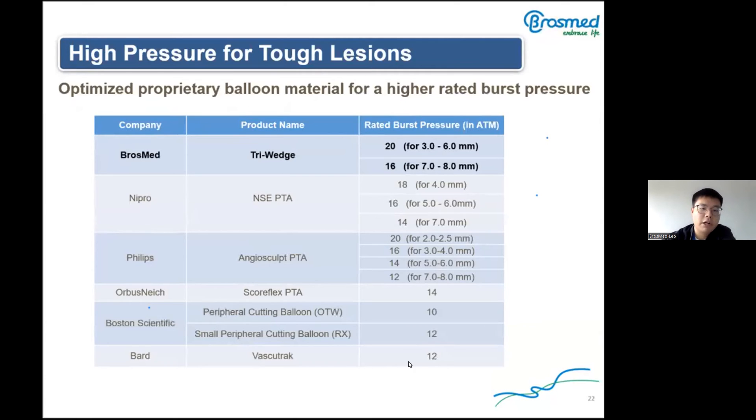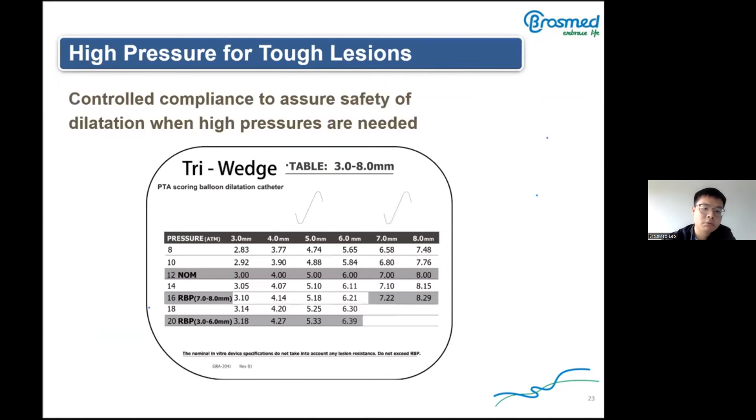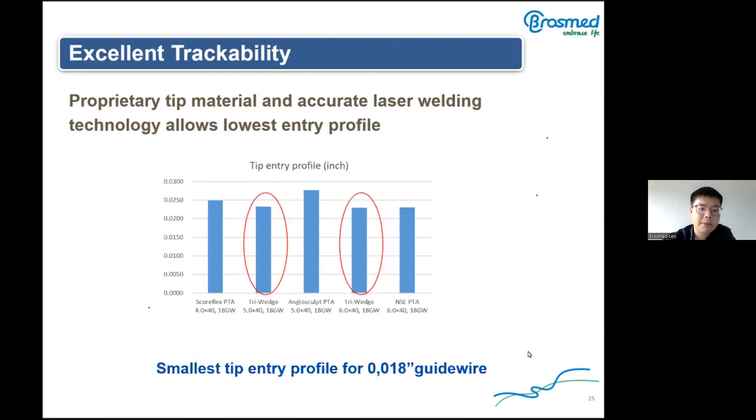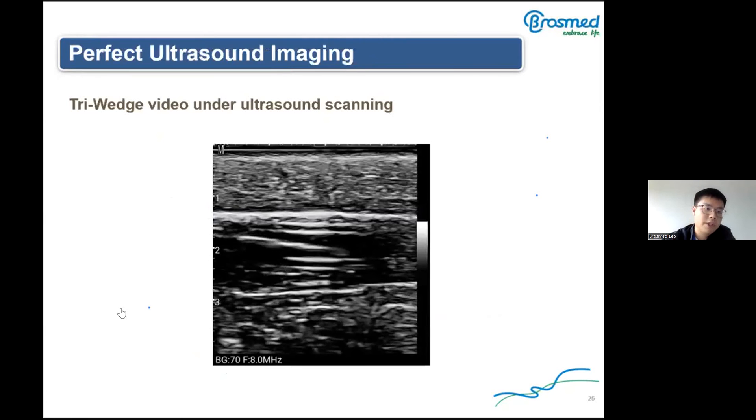Sometimes hard lesions require high pressure. The rated burst pressure of the Tri-Wedge is higher than similar competing products, indicating it can be safer during surgery. The Tri-Wedge uses a non-compliant balloon, so under different pressures the diameter changes very little, achieving accurate vessel dilatation. Accurate laser welding technology allows the lowest entry profile, improving the product's trackability and crossability. Compared to products on the same configuration, the tip profile of the Tri-Wedge is smaller. The Tri-Wedge can also be clearly visualized under ultrasound scanning.